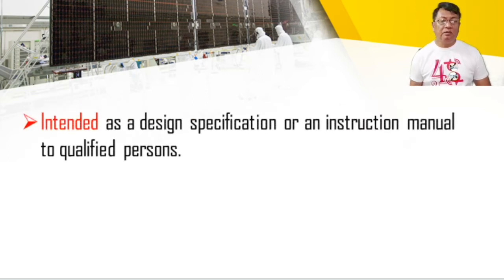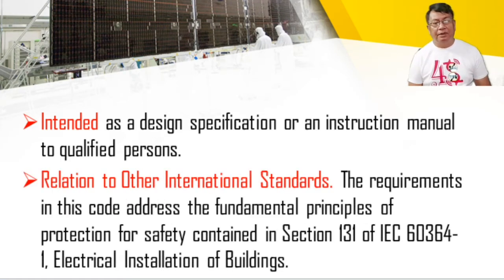Okay, so this spec also is intended as a design specification or an instruction manual to qualified persons. Our designer refers to the scope of authority and job of the professional electrical engineer. When you are going to design, this Philippine Electrical Code is intended to be our manual and guide, to be able to specify the design, the wire size, and the specification of any devices that shall be installed in the project.